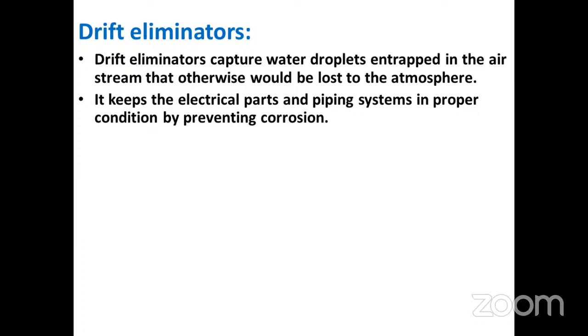What are the advantages? First major advantage is saving of water. Second thing, the electrical parts and piping system are kept in proper condition by preventing corrosion. Actually, in the thermal power station, it's a huge problem. They add sulfuric acid to the cooling water to control algae growth and so on. But due to this water carryover, it corrodes the nearby iron structures in the surroundings. I've seen many iron structures damaged, even handrails and everything. The staircases, everything got damaged in the thermal power station.